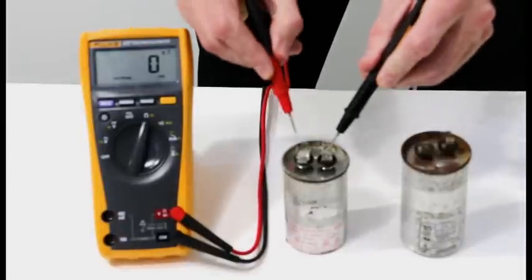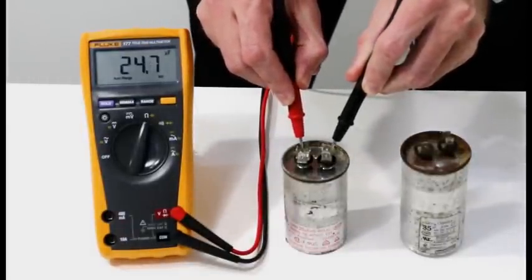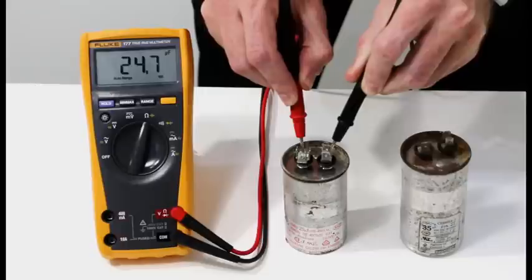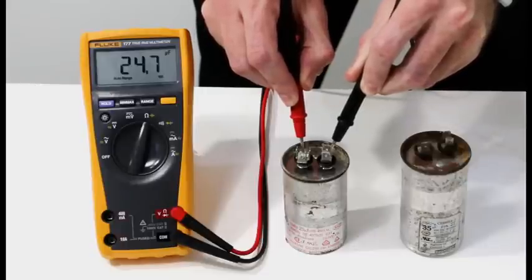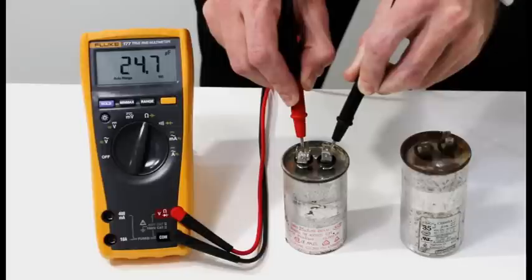I then take my test leads and put them on the ends of my capacitor. This one I'm measuring 24.7. This is my 25 microfarad capacitor. So this one to me is working perfectly. It's within the 5% tolerance specification.